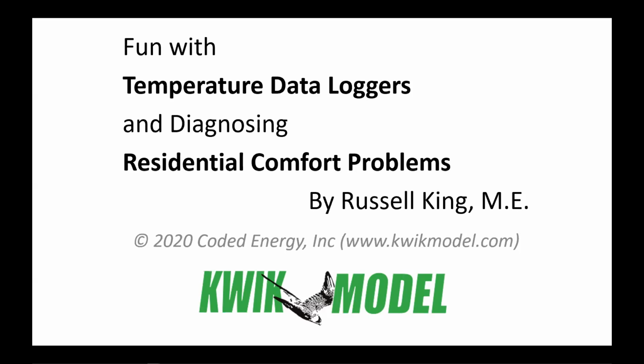Sorry. No problem. So imagine telling these homeowners your problem is your equipment's too big and you need smaller equipment. And they're all up in arms and they have their attorney and everything. Well, that didn't go over very well. And so I said, well, the only way to prove it to you is to monitor your houses, to actually monitor the outdoor temperature, the indoor temperatures, and when the equipment runs. Okay. And so I proposed monitoring these houses using something called data loggers.